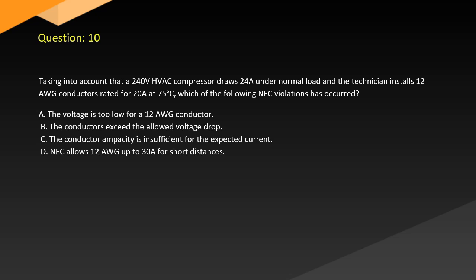Question 10. Taking into account that a 240 volt HVAC compressor draws 24 amps under normal load, and the technician installs 12 AWG conductors rated for 20 amps at 75 degrees C, which of the following NEC violations has occurred? A. The voltage is too low for 12 AWG conductor. B. The conductors exceed the allowed voltage drop. C. The conductor ampacity is insufficient for the expected current. D. NEC allows 12 AWG up to 30 amps for short distances.